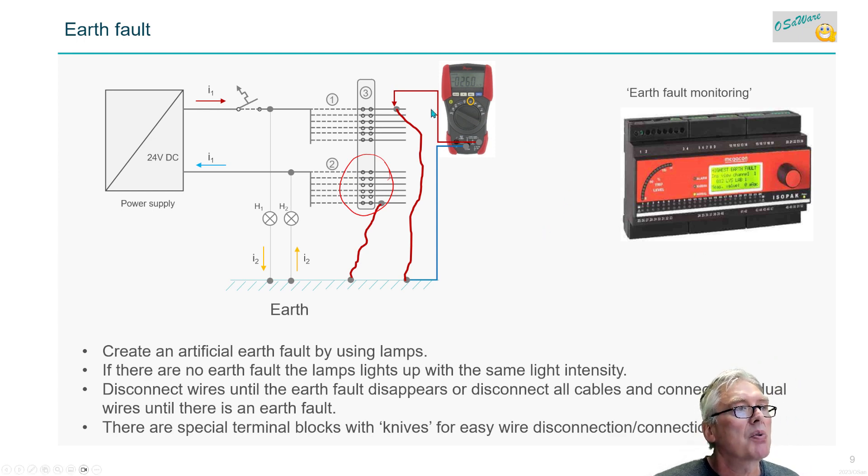You can use two lamps. If there's no earth fault in a 24-volt circuit, you should have 12 volts here, 12 volts here, and they should light with equal strength, same intensity. Then you can disconnect all wires and reconnect and disconnect one wire until the lamps start to glow with equal intensity. Then you have located your faulty wire.